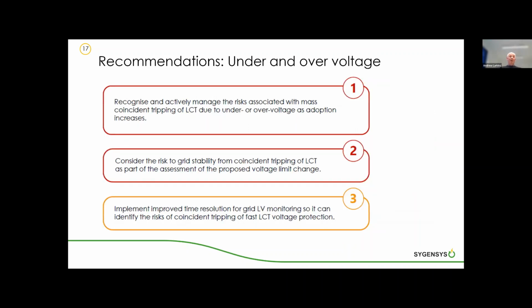So within the section looking at under and over voltage, we are making some specific recommendations. Firstly, to recognise and actively manage the risks of mass coincidence tripping due to under and over voltage being experienced by low carbon technologies. Specifically, under and over voltage tripping has been considered in detail with regard to generation in the past. What we would highly emphasize from this project is that we will see similar effects from loads going forward.